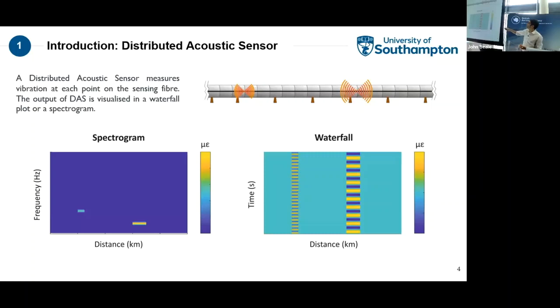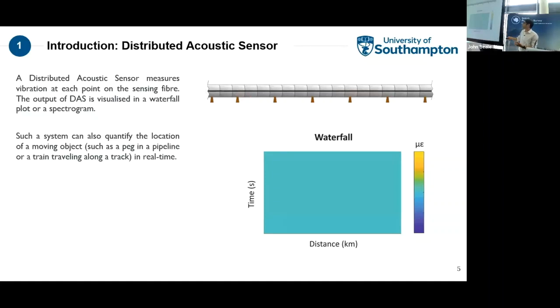So going back to the pipeline. So if you have a leakage on the pipeline, if there's someone's walking on the pipeline, someone's digging, you should be able to use that as a strain gauge, as a microphone. At those points, measuring the strain that that vibration imposes on the fiber, the frequency, the amplitude, all the features. And if you do the Fourier transform, you can do the spectrogram. So you can look at the frequency components of those vibrations along the distance. And of course, because it's a real time system, it's a dynamic system, if there's a moving object in a pipeline, if there's a pig going down the fiber, you should be able to have this diagonal line, which shows the location of that, the speed of it, the noise that it generates, so on and so forth.